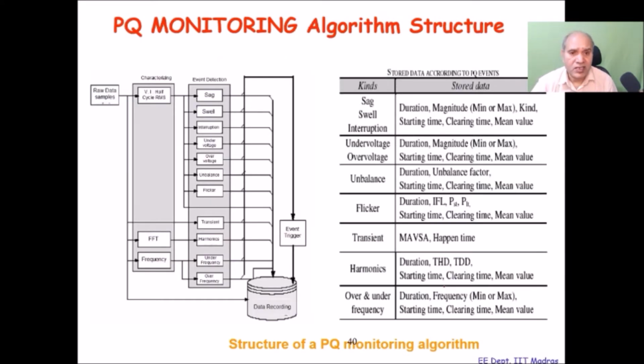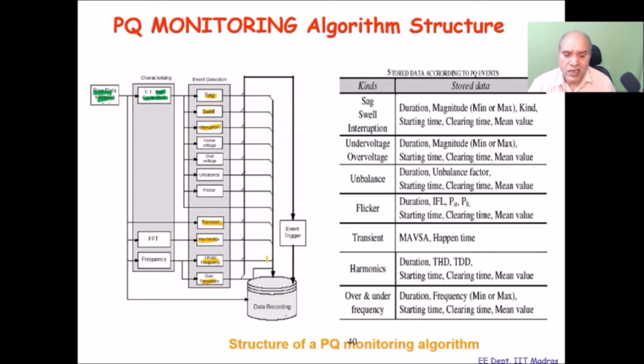And what are these parameters which are read through this monitoring system? You can see it here. At this stage we have raw data. Okay, so you can see here that we have raw data, and then we have the measurement characterization in terms of the half cycle RMS or full cycle RMS, and then we have characterization of event detection in terms of the sag, swell, and interruption, and so on, transient, harmonics, under frequency, over frequency, and so on. And finally, there is data recording where all information is stored, and which is also used to transmit this information to the personnel operators of the system. Okay.